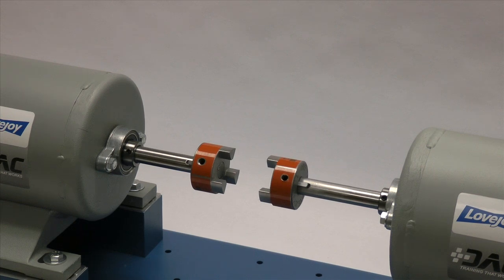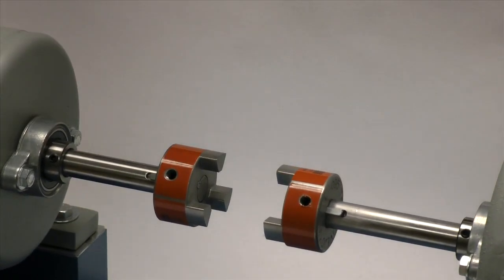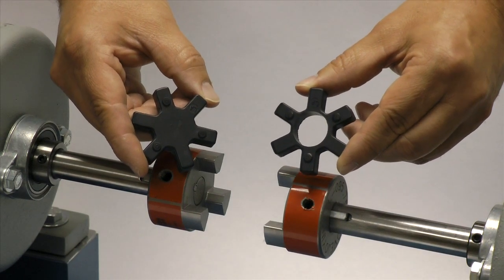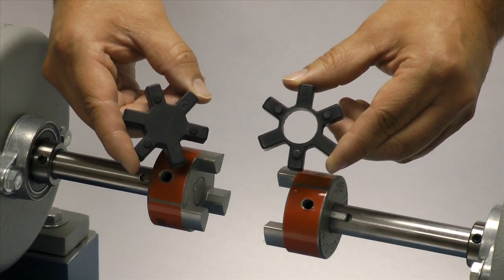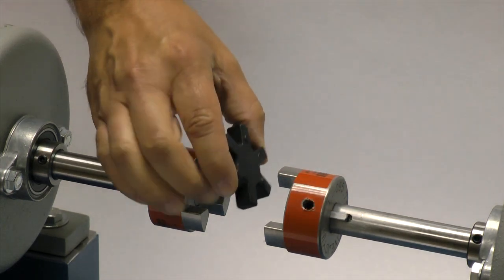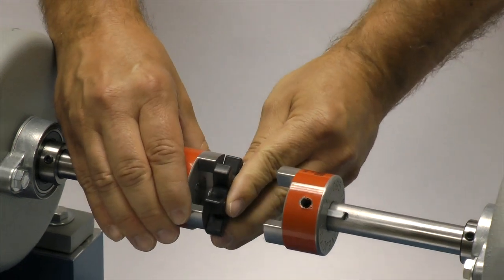Next, we will insert the spider into one of the jaw coupling hubs. If the final shaft separation is going to be less than the actual width of the spider, you may need to use an open center spider. Please remember that open center spiders are limited to 1800 rpm. For our installation, we will be using a closed center spider.